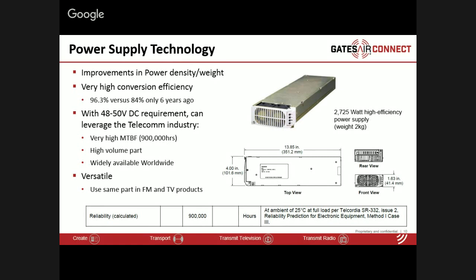These new power supplies operate from 48 to 50 volts and leverage the telecom industry's power supplies. These are very standard power supplies in the telecommunications business, so they're high production, high demand devices, readily available with very high mean time between failure ratings. The particular power supply we use is made by General Electric, with a 900,000 hour mean time between failure rating. Very rugged, very reliable, available worldwide and through many vendors.